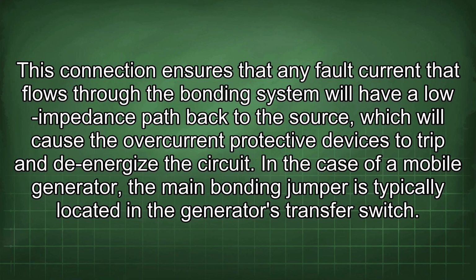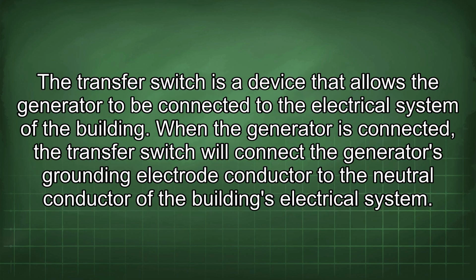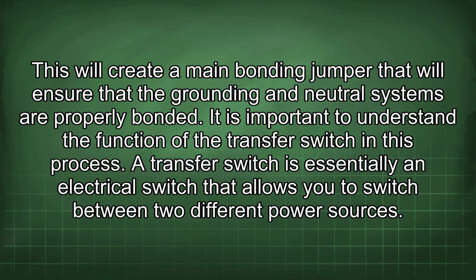In the case of a mobile generator, the main bonding jumper is typically located in the generator's transfer switch. The transfer switch is a device that allows the generator to be connected to the electrical system of the building. When the generator is connected, the transfer switch will connect the generator's grounding electrode conductor to the neutral conductor of the building's electrical system. This will create a main bonding jumper that will ensure that the grounding and neutral systems are properly bonded. It is important to understand the function of the transfer switch in this process.